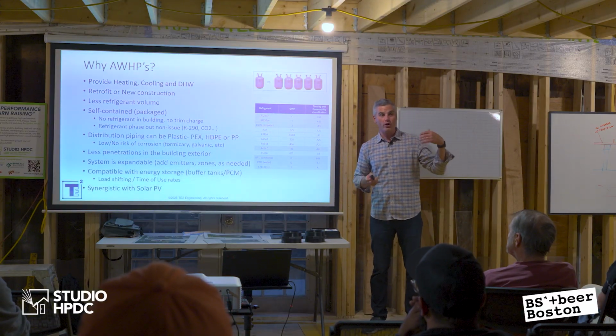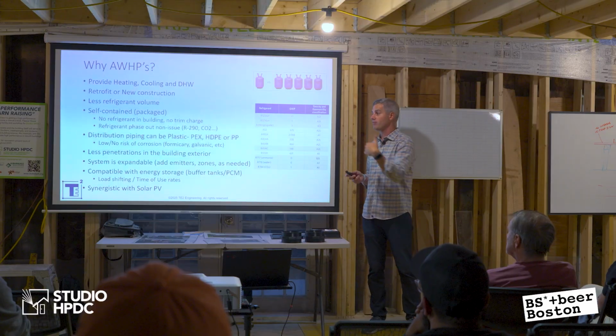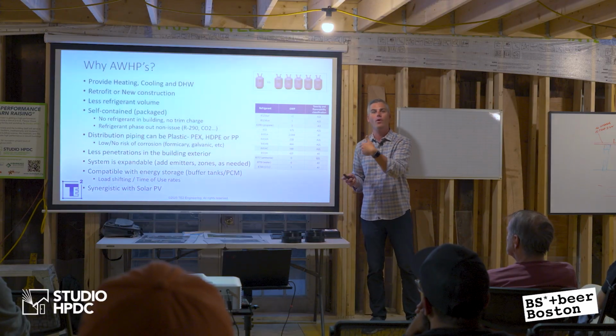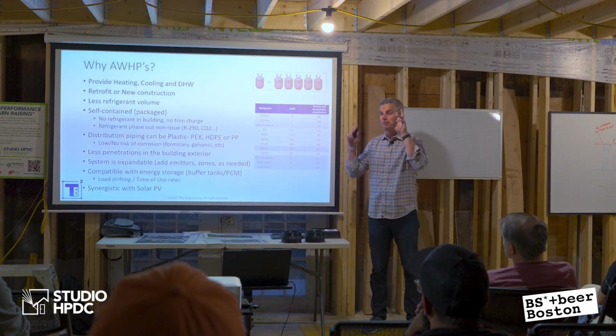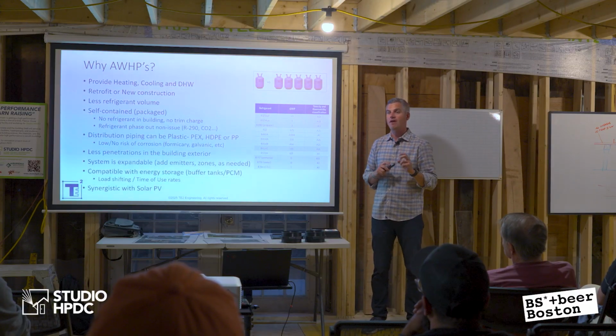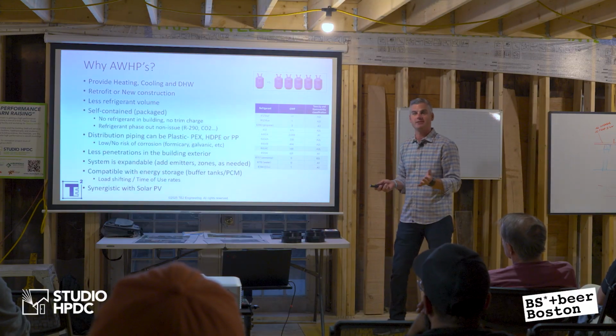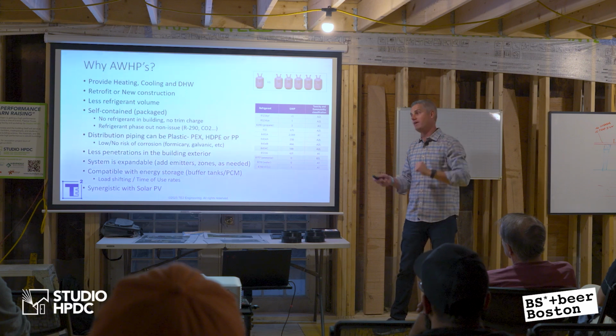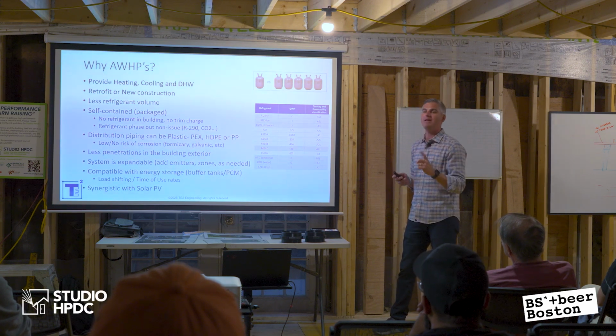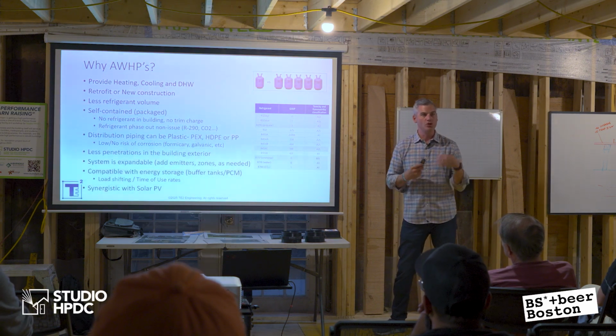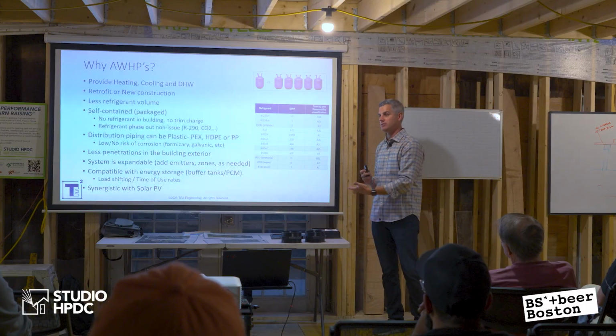I think you guys have all probably heard about R410A going away, right? Being replaced with A2Ls, with R32, R454B, these mildly flammable refrigerants. If I have a failure of a 410A system, and let's say the air handler fails or the outdoor unit fails, I have to replace the entire system. The new refrigerant is not compatible with the old systems.